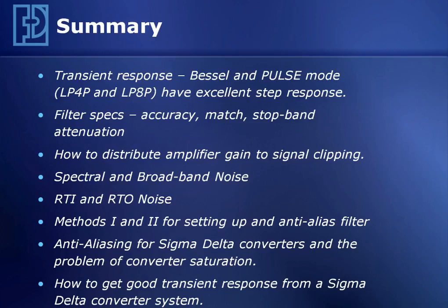Okay, to wrap this up, as a summary, we talked about transient response and looked at step response of various filters and found that the Bessel and pulse mode, the LP4P and LP8P, had excellent step response. They also have very good phase linearity, and they're great choices for time domain measurements. We also looked at the step response of some sharper filters like the LP8F, and found that those are underdamped, have lots of overshoot and ringing, and may not be the best choice for shock and transient type measurements.